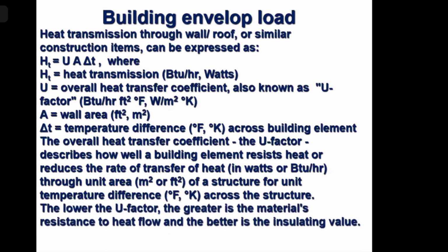The overall heat transfer coefficient, U factor, describes how well a building element resists heat, or reduces the rate of heat transfer through unit area of the structure per unit degree difference of temperature. This is called U factor. So from the equation HT equal to UA delta T, you can see the lower the U factor, the lesser is the heat transfer. So we would prefer lower U factor. That means we would prefer to use a building material which has a lower U factor so that outside heat coming inside will be less.